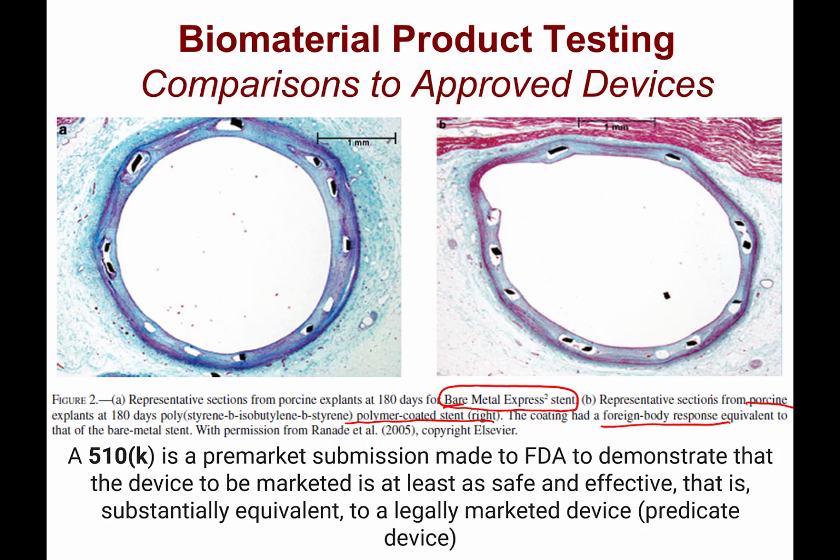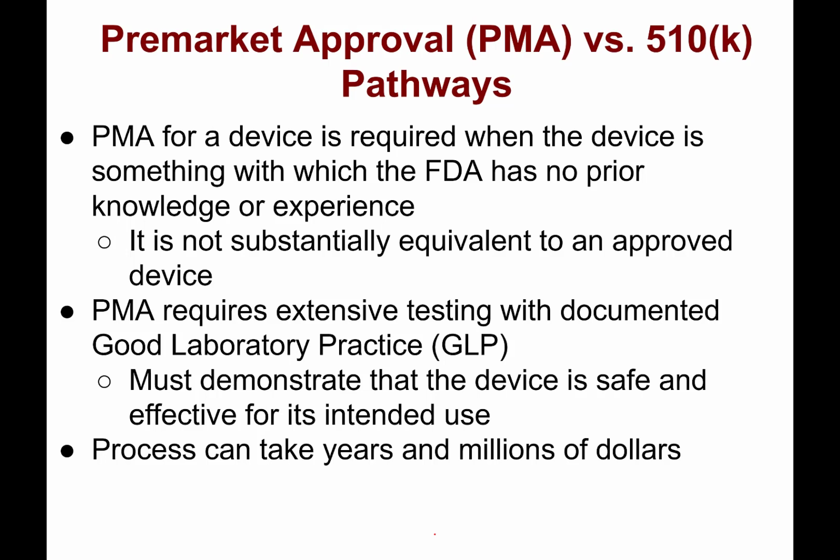So the 510K is a pre-market submission made to the FDA to demonstrate that the device to be marketed is at least as safe and effective. That is, it is substantially equivalent to a legally marketed device. And so this is this key concept of a predicate device. The rationale is, well, it's not any more dangerous or less effective than something that's already out there, so it must be okay to proceed with.